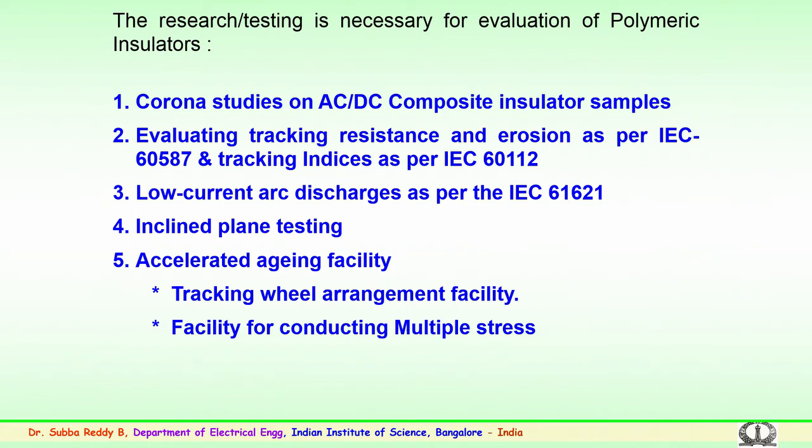Then there are reliability tests prescribed by IEC 61621, particularly the low current arc discharges, the lower current continuous discharges on the sample, which should be created to see whether the discharges damage the surface and whether the material loses its hydrophobicity.